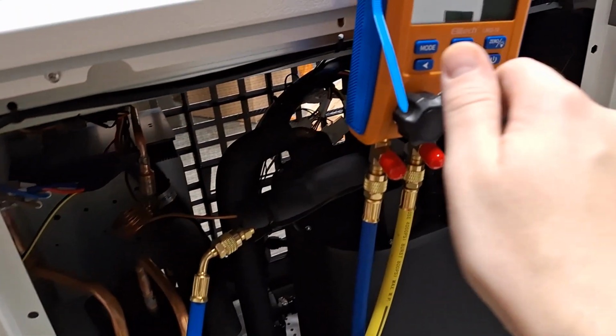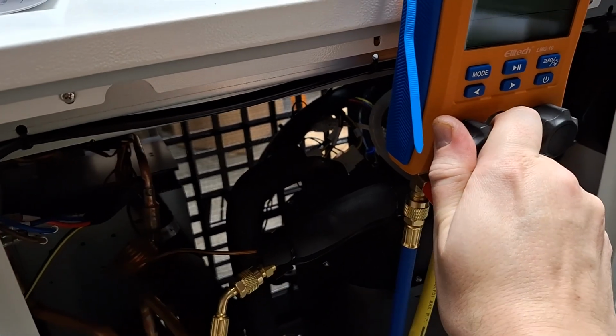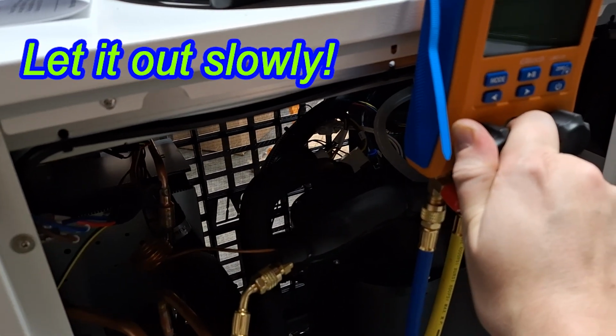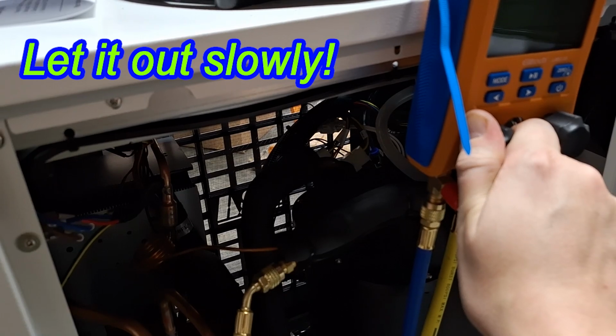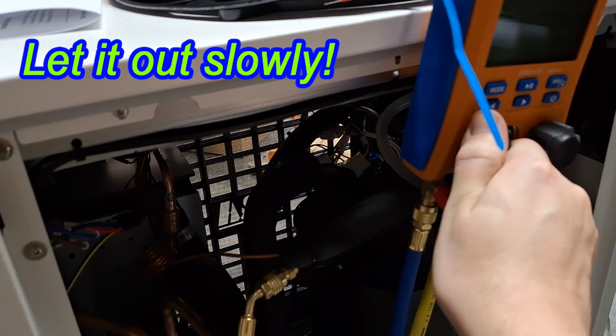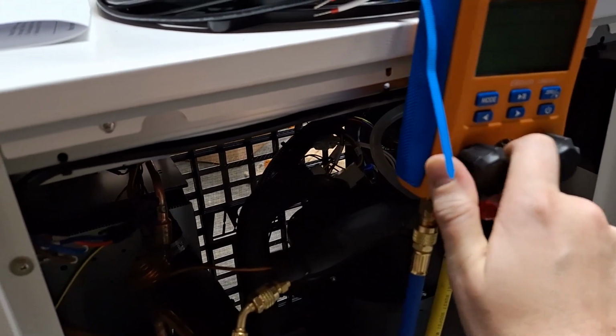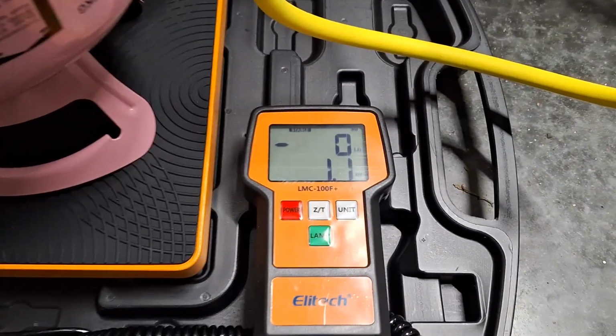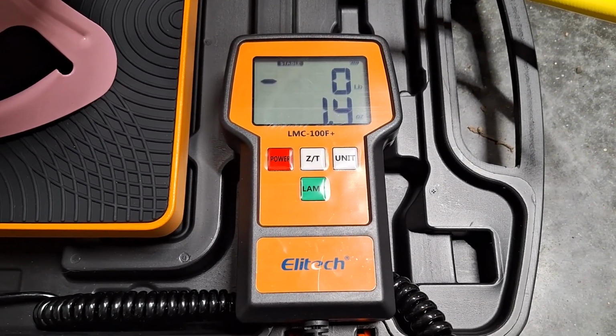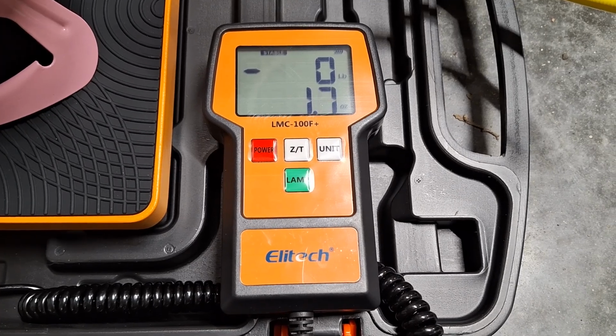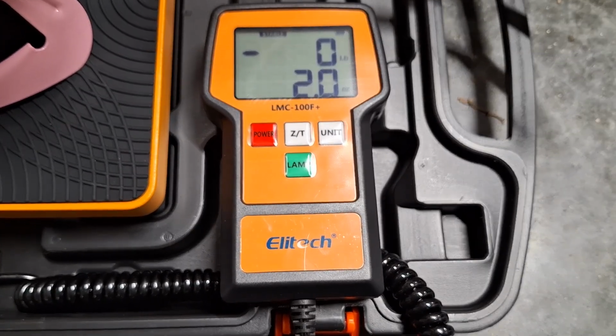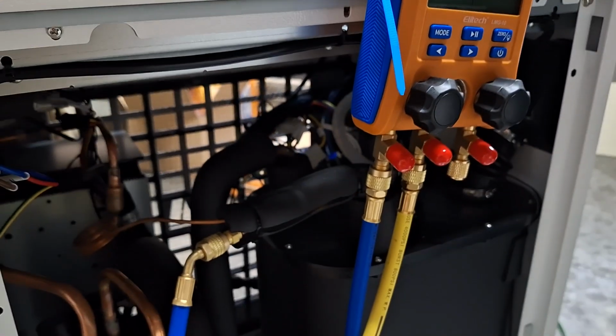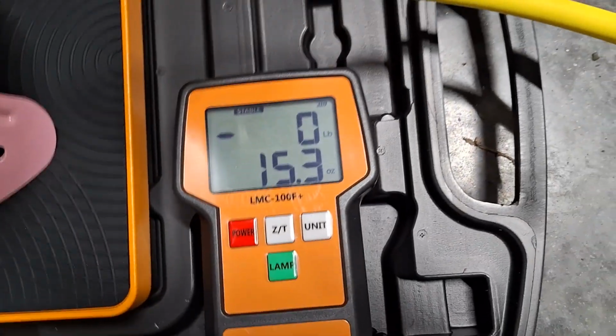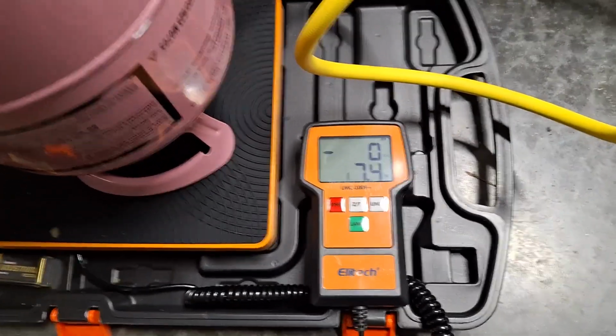Now I have the tank upside down on the scale set to 0. I'm adjusting the manifold gauge to get the perfect amount of liquid and gas R410A into the chiller itself. I've removed the vacuum gauge from the chiller, and I have the blue line from the manifold gauge going directly into where the vacuum gauge was on the chiller itself.